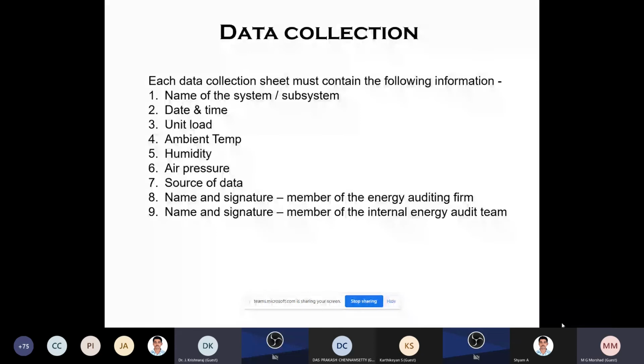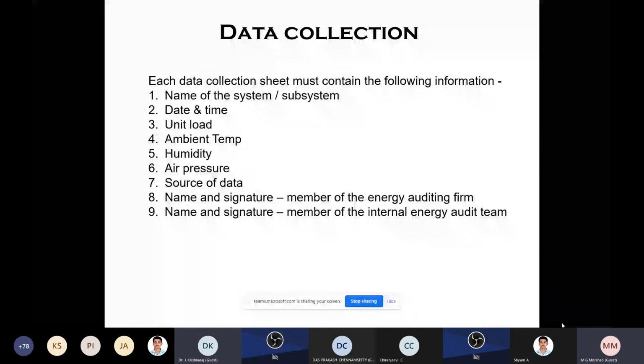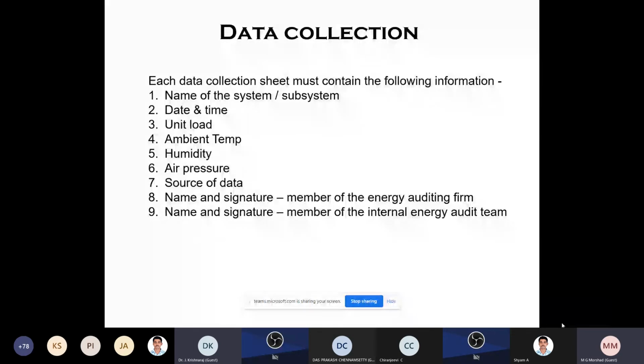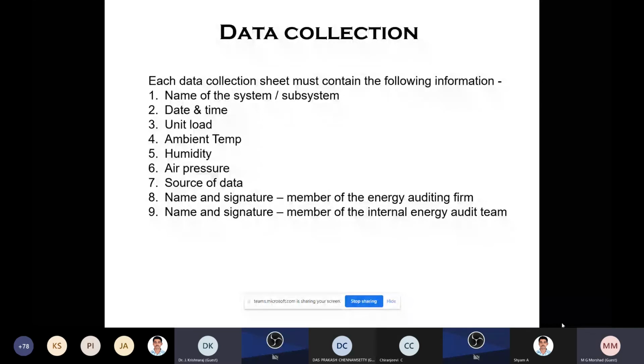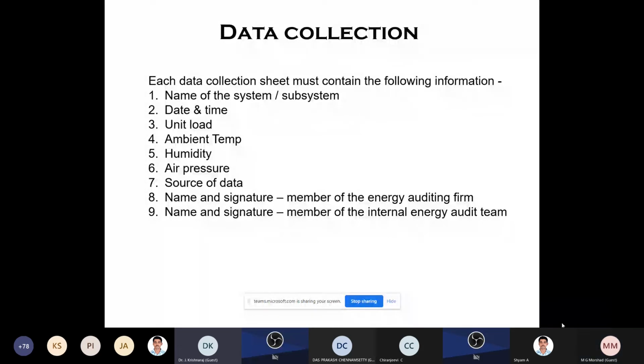See, these are all the things that should be pointed out. Data sheet means one book or one log sheet will be there. Suppose you are going to take the data of the boiler. In the sheet itself, before collecting the data, you have to put the name of the system or subsystem, boiler efficiency, then date and time, unit load, ambient temperature, humidity, air pressure, source of data, the name and signature of a member of the energy auditing firm, and the name and signature of a member of the internal auditing firm. So it will establish that you have collected the data in presence of the energy audit team.